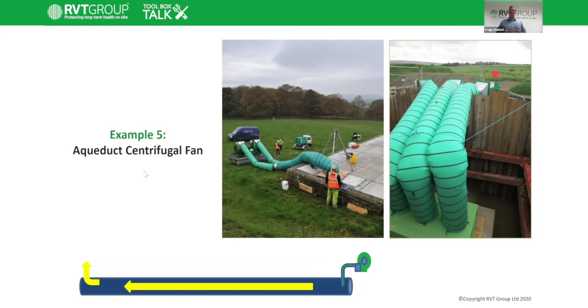So again, potentially not such a common application, but it's something we have a lot of experience in and we have done successfully. So aqueducts and other similar tunnels that have restricted openings at either end. So the tunnel may be accessed by a shaft or a hatch. In this application, what we feel is the most beneficial way is to actually use the tunnel to act as a duct itself. The diagram at the bottom of the slide there, you see the fan with the ducting connecting into the tunnel. The ducting is sealed into the tunnel, which then forces the fresh air through the length of the tunnel, which then comes out at the opposite end of the tunnel via a shaft.